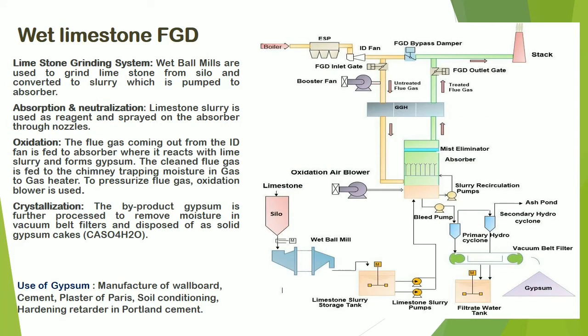Wet limestone FGD, which is widely used in power plants nowadays. Limestone grinding system: wet ball mills are used to grind the limestone from the silo and convert it to slurry, which is pumped to the absorber. Absorption and neutralization: limestone slurry is used as a reagent and sprayed into the absorber through nozzles. Oxidation: the flue gas coming from the ID fan is fed into the absorber where it reacts with lime slurry and forms gypsum. The cleaner flue gas is fed to the chimney; a gas-to-gas heater traps moisture and an oxidation blower pressurizes the flue gas. Crystallization: the by-product gypsum is further processed to remove moisture in vacuum belt filters and disposed of as solid gypsum cakes.